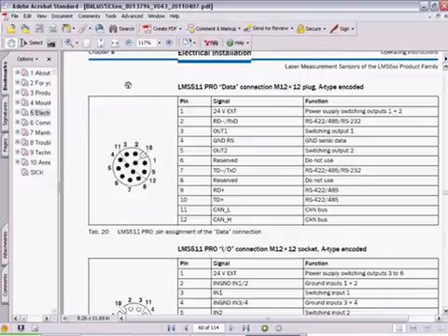One final point is the connectivity, and because we can actually supply our own external voltage to the outputs, that means we have to provide 24 volts to the unit, and that goes in on pin 1 here, you can see. So if you're using the same supply as the LMS main control supply comes from, just put a loop from the supply to the LMS through into pin 1 here, and then output 1 and output 2 go off to your host, and obviously using ground as the volts. So as simple as that, but it's important to remember to connect this to the 24 volt supply to the unit.